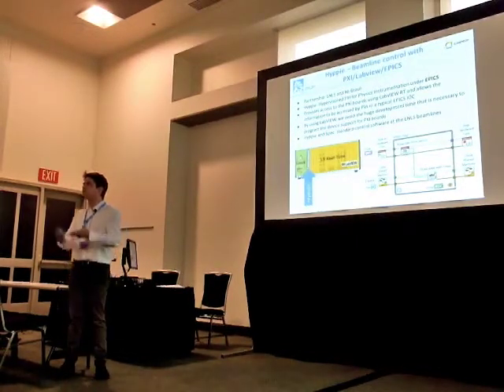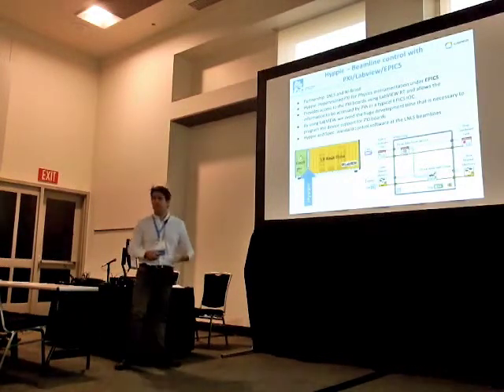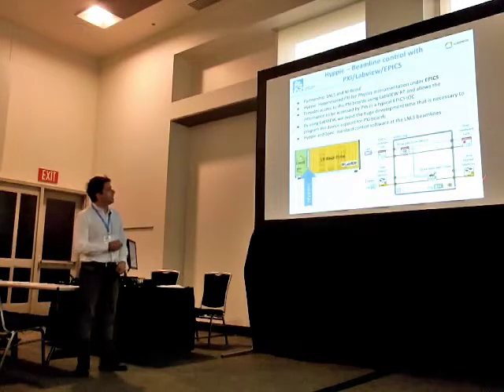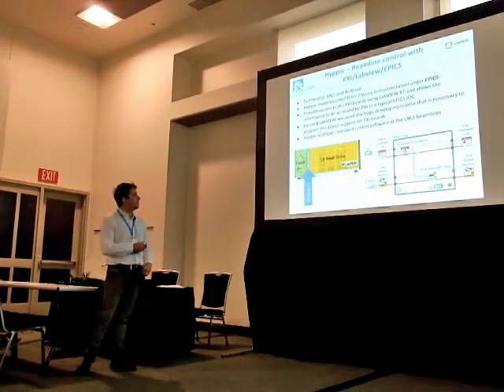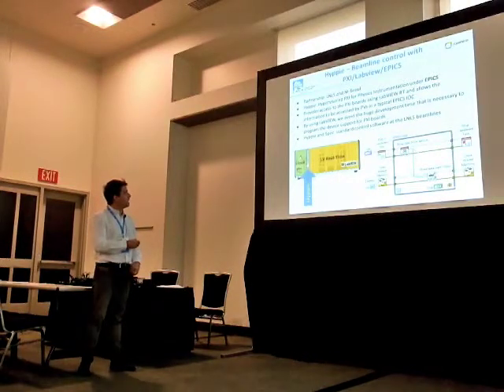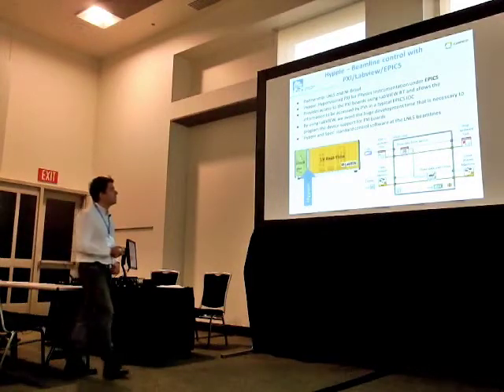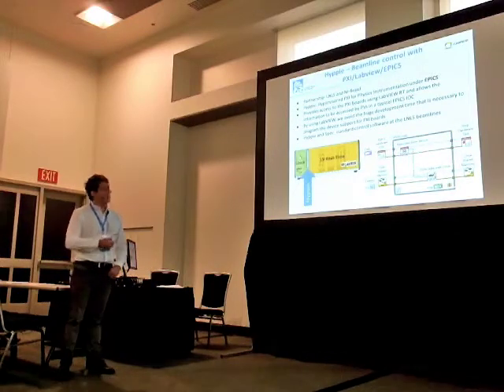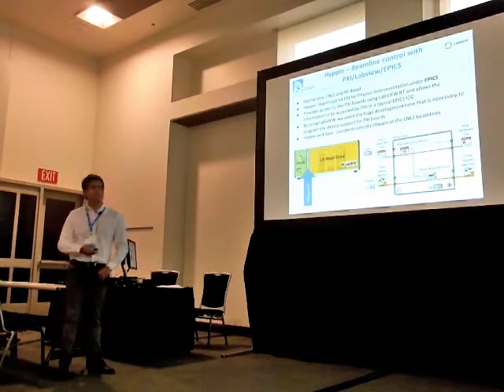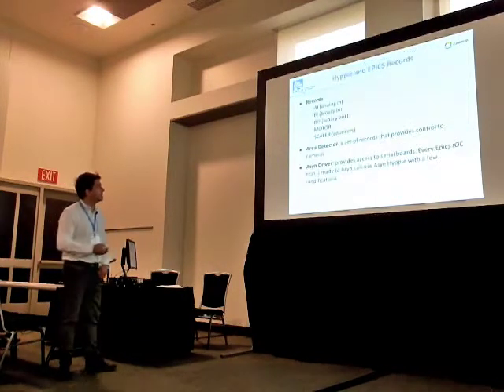For several reasons, we had most of our software for analysis, data acquisition and scripts written in EPICS in the community, so we wanted to make use of that. Together we developed this platform that uses shared memory through a software which we call Hyppie, and that is able to collect data from LabVIEW in real time and propagate it into the EPICS server so that we can have all the data available on our network. This was a major important development for us. Now all of our beamlines are running in this scheme and it's very robust. We basically have a standard way of controlling beamlines.